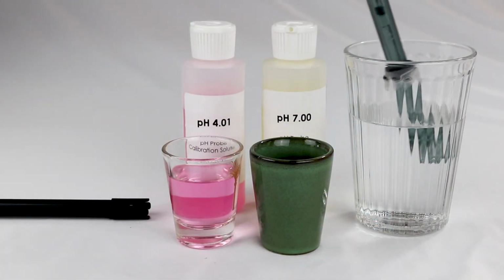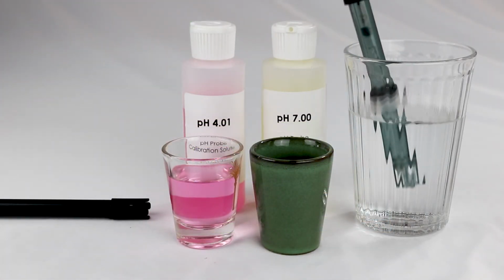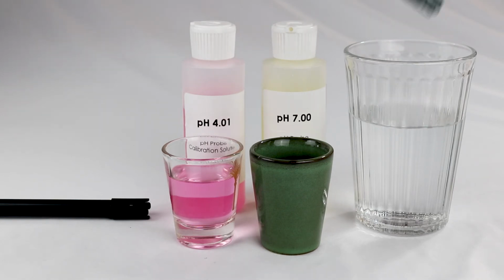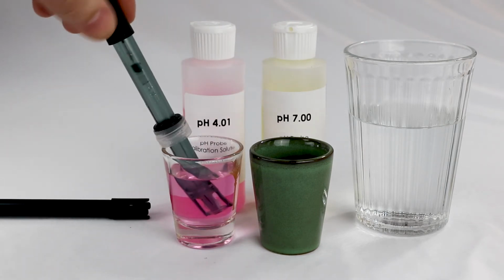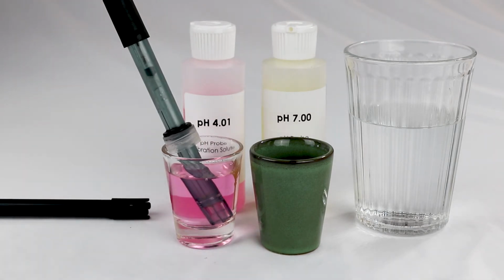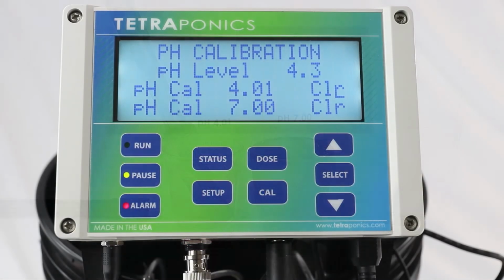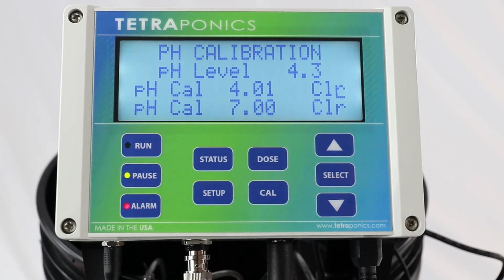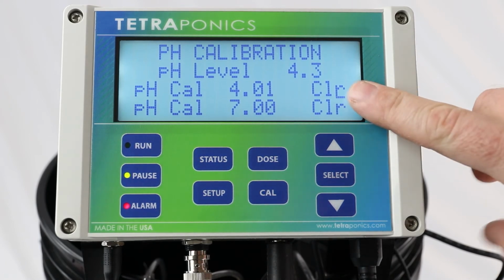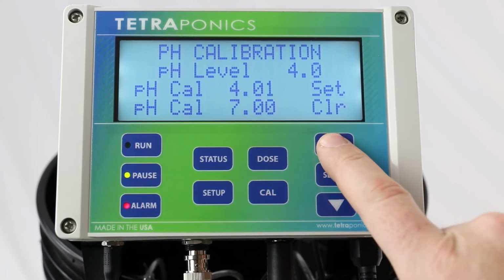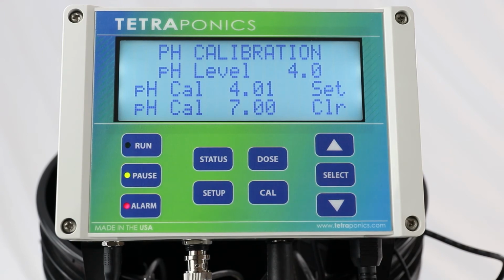Gently rinse the tip of the probe with room temperature tap water and shake off the excess. Place the probe in a glass containing 4.01 pH calibration solution. The solution should cover the entire tip of the probe. Wait about 1 minute for the reading to stabilize. Now, with the cursor next to the 4.01 selection, press the up arrow to calibrate the probe at 4.01 pH.